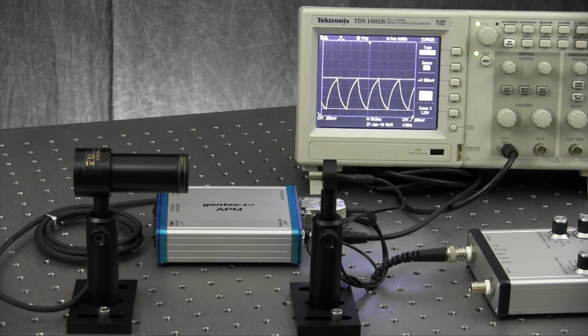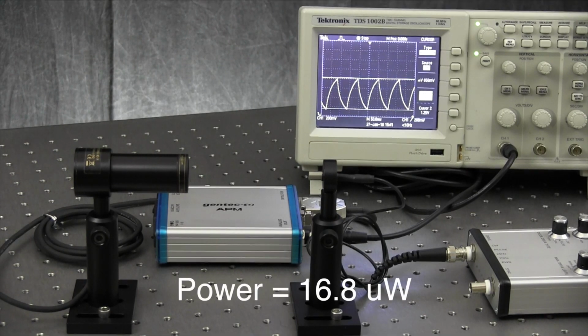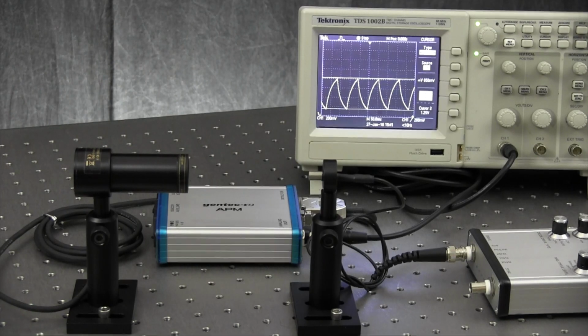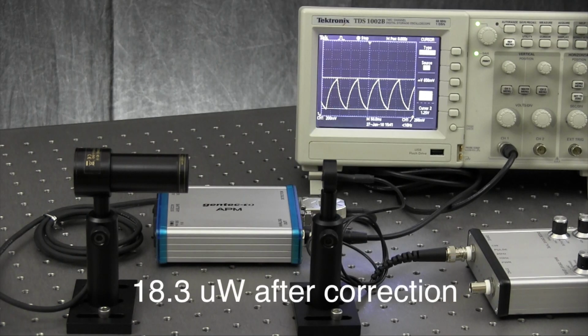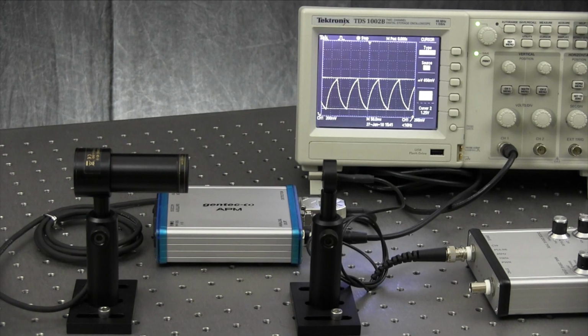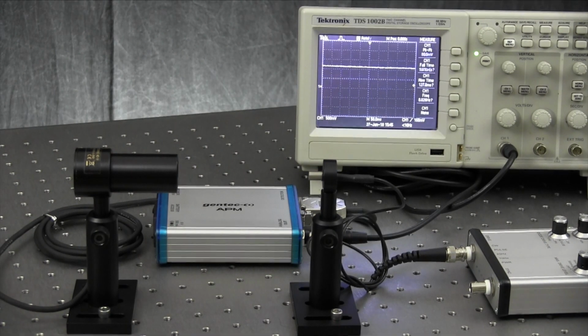Now, to calculate the laser power, you divide 656 millivolts by the voltage responsivity of the UM9B, which is 39 kilovolts per watt, and that equals 16.8 microwatts. If we correct this for the window loss of 8%, we'll get a laser power of 18.3 microwatts. That's how you use a UM9B and APM to measure a chopped or modulated laser.